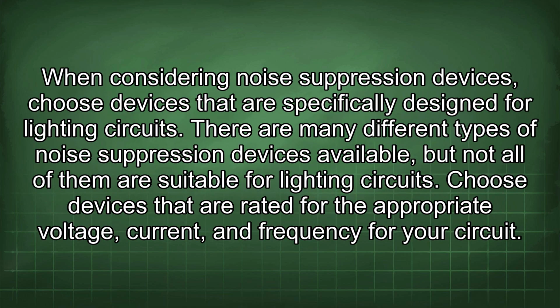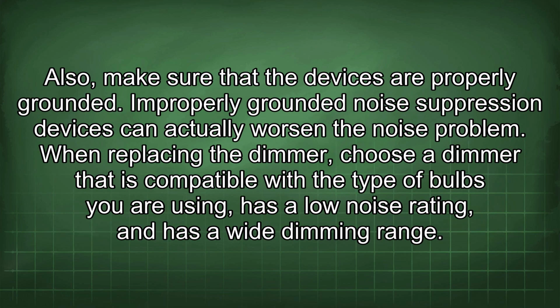When considering noise suppression devices, choose devices that are specifically designed for lighting circuits. There are many different types of noise suppression devices available, but not all of them are suitable for lighting circuits. Choose devices that are rated for the appropriate voltage, current, and frequency for your circuit. Also, make sure that the devices are properly grounded. Improperly grounded noise suppression devices can actually worsen the noise problem.